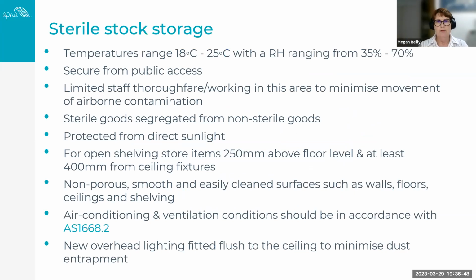Sterile stock storage, a very important part again of the process. Ideally you want to store your reprocessed items behind closed cupboards, drawers, or lidded containers, preferably not out on open shelving, especially if you have a reprocessing area that's quite small. The temperature range in accordance with the standard for sterile items is between 18 and 25 degrees Celsius, with a relative humidity of between 35 and 70%. It's very easy to put a hygrometer where you store your sterile items just to see what the temperature is. I always recommend doing that so that you've got some idea that you're within the range.